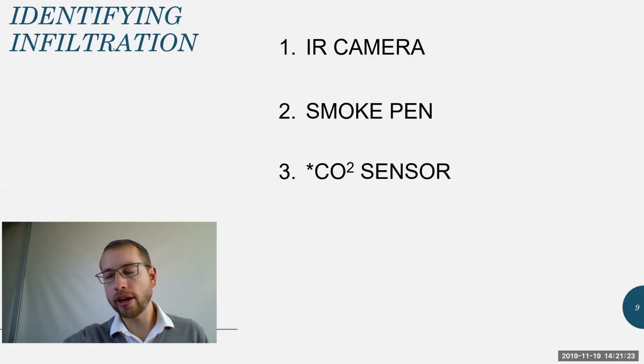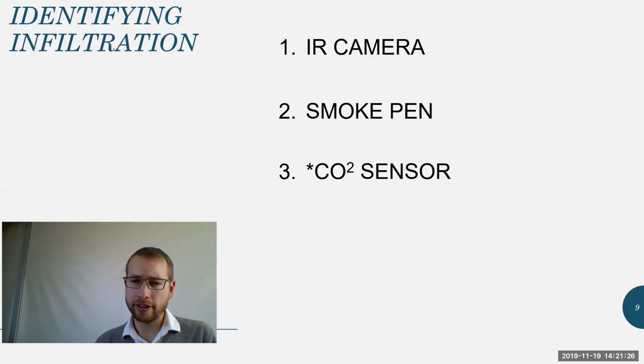The other tool that you can use is a carbon dioxide sensor. Now, I wouldn't recommend using it for full commissioning. It can be really tough to get a calibrated gas mixture. But if you are doing an energy audit, I like to set up a carbon dioxide sensor or two just to get a sense of what the CO2 level is like. And if it is, say, way higher than 400 parts per million, then you know that maybe the ventilation system isn't working properly. Or if it's staying at 400 even, then they might be over-ventilating the space, right? Better to be over-ventilated than under-ventilated for those of us that like to breathe.